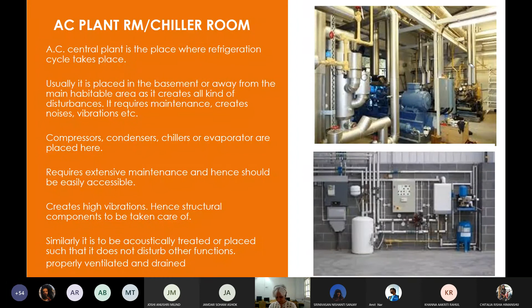So there are actually drain boards which are kept below your evaporator chillers, which is connected to the drain pipe, okay? And you will need to take the drain pipe out of the building like a rainwater pipe, and that will be 6 inches. So all this has to be done. Okay, that's why it has to be properly ventilated and drained. Now imagine if you are in a basement. So either you can take this water and push it into the UG rainwater harvesting tank, okay? Or you will have to put it into the sump where it will be pumped out. But you will have to show all this, okay?